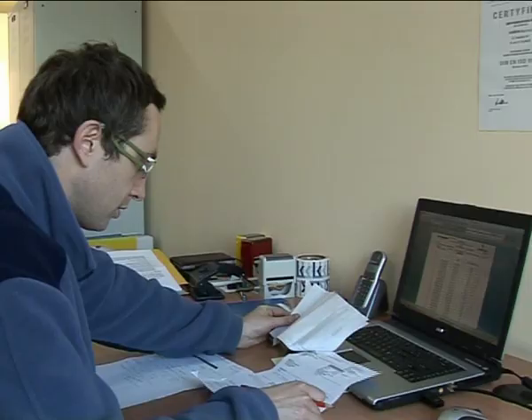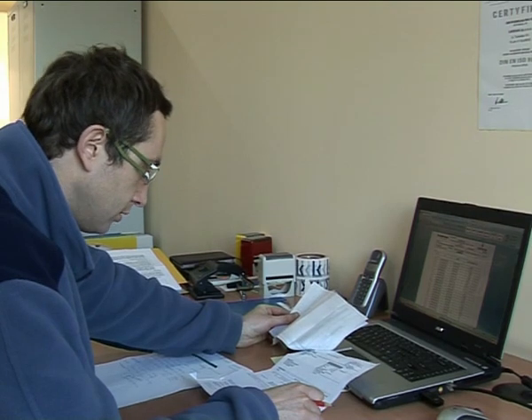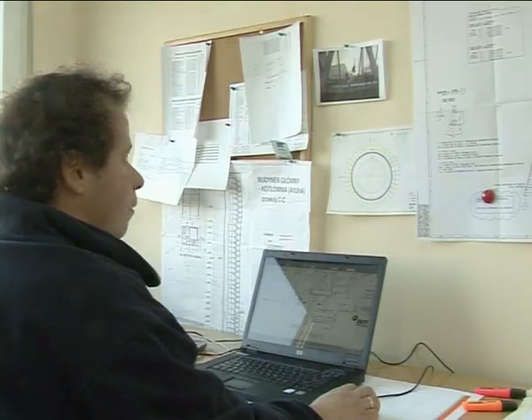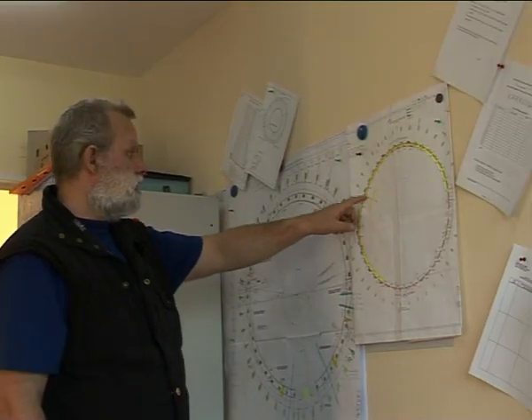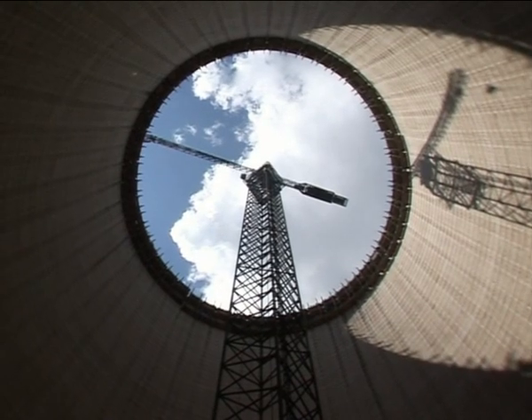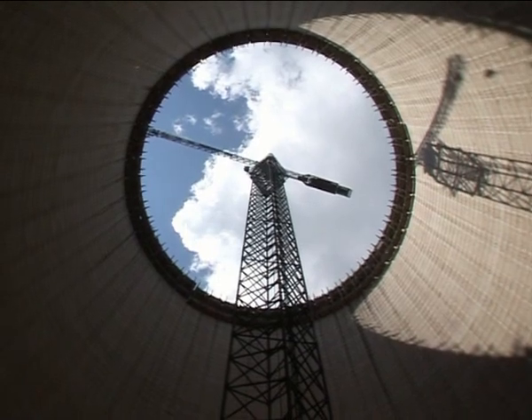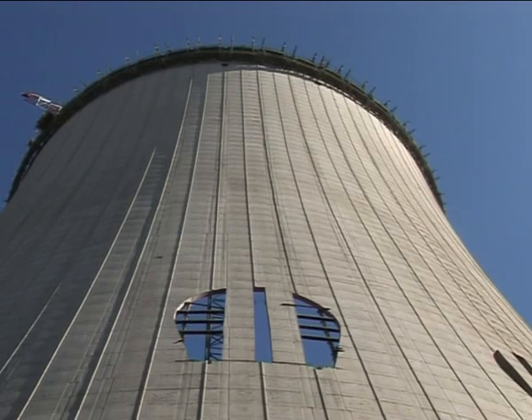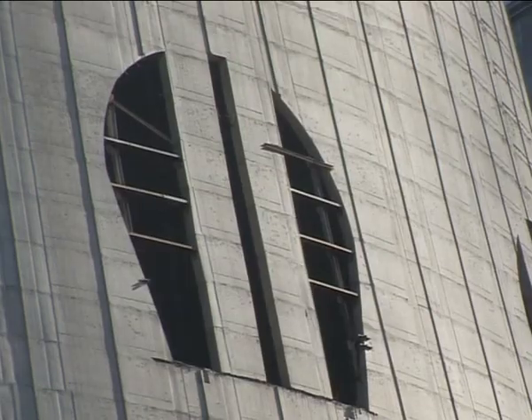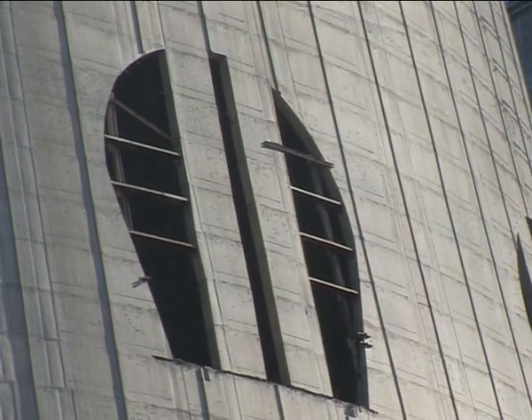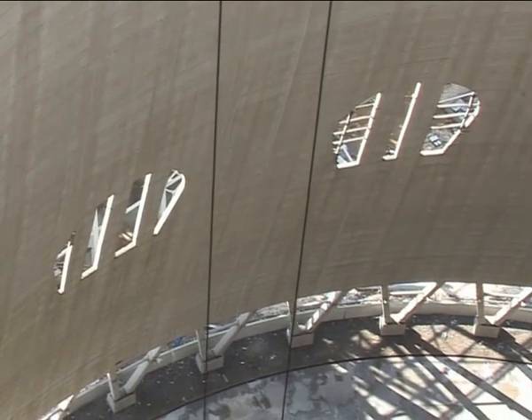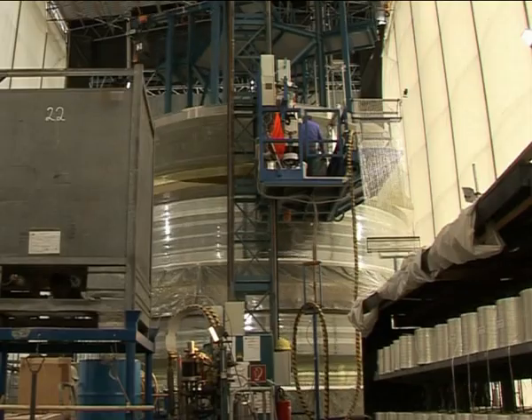Now let us go back to the construction of the cooling tower. The cooling tower will have two tasks. Firstly, to cool water for the power unit installation, and secondly, to act as a chimney venting combustion gases after their cleaning in absorbers. Two holes were designed in the reinforced concrete shell at a height of about 40 metres for fitting the exhaust pipes for the combustion gases from the boiler.